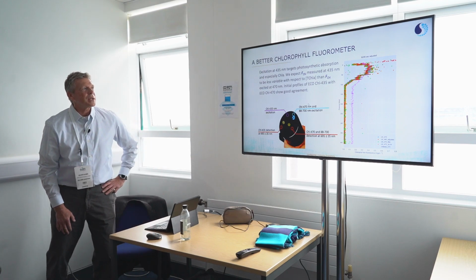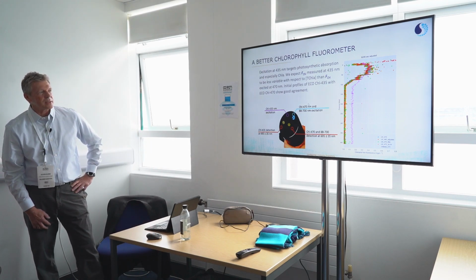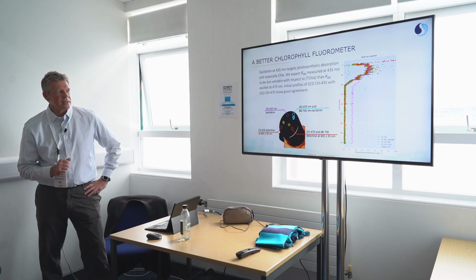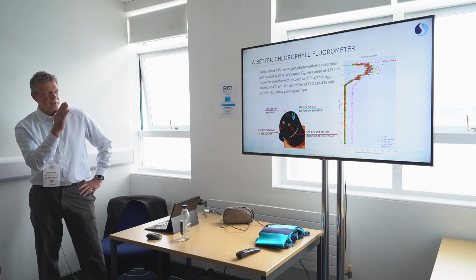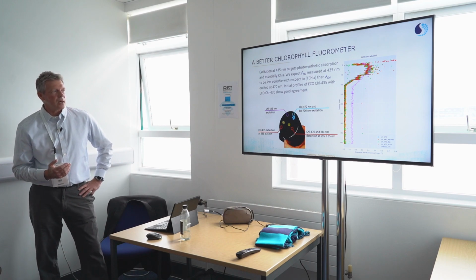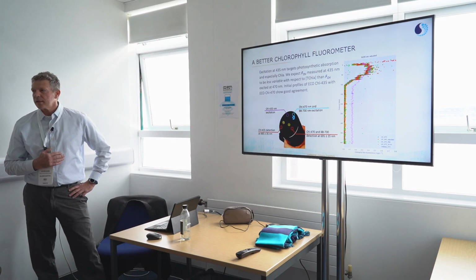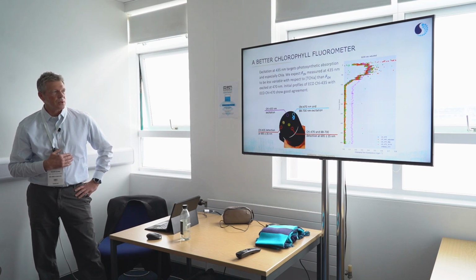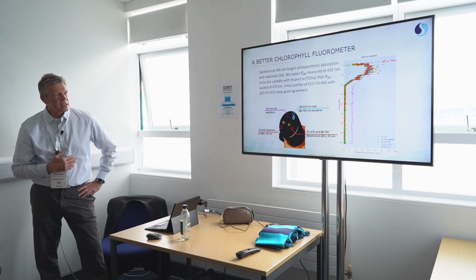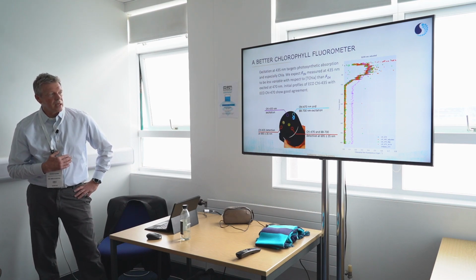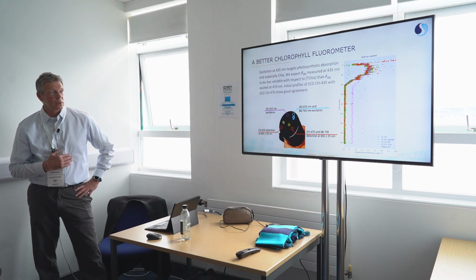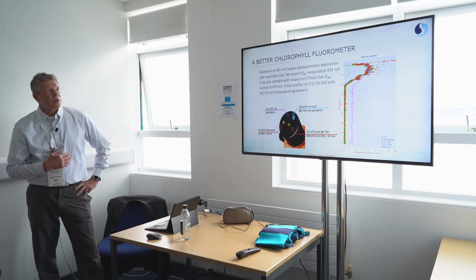So what's shown here is an ECO triplet at the bottom with traditional 470 chlorophyll excitation and the turbidity at 700 nanometers on the right side of it. And normally this triplet ECO would contain on the left side a CDOM or an FDOM sensor. In this case, this has been replaced by a 435 nanometer chlorophyll excitation. So you have a dual excitation for chlorophyll here.